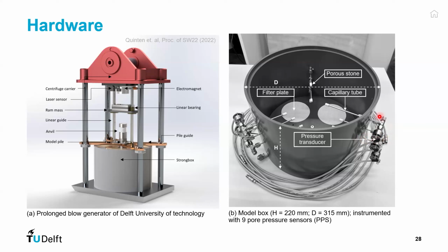And as you can see, the whole system with all of the connections, etc., is quite bulky. So in this way, it is better to make sure that we do not affect our measurements too much. Now, then, of course, the question is, how do you measure something inside the Strongbox if your sensor is located outside the Strongbox? And that is where these capillary tubes come in.